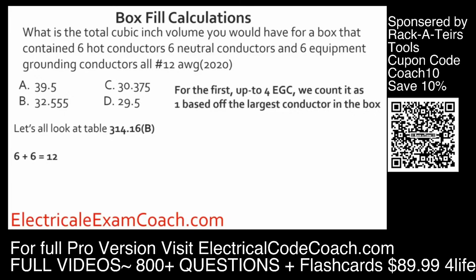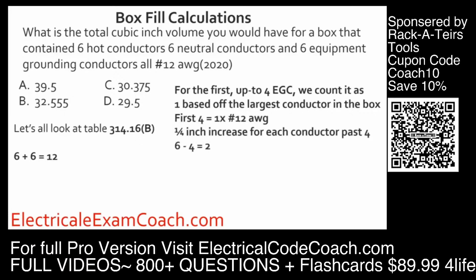We're going to, for the first 4, it's going to count as 1. So we need to figure out how many we are past 4. We have 6 total minus that 4. That means we are 2 past 4. For each one of those, it's going to be a 1/4 inch increase. Take 2 multiplied by 0.25, that equals 0.50.